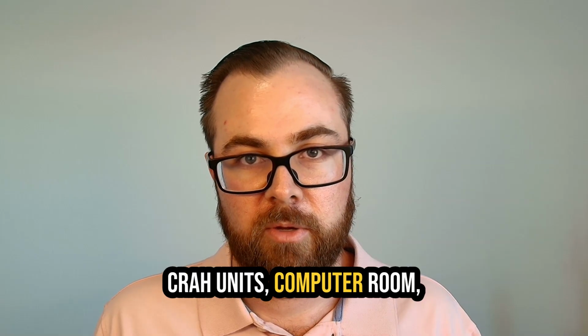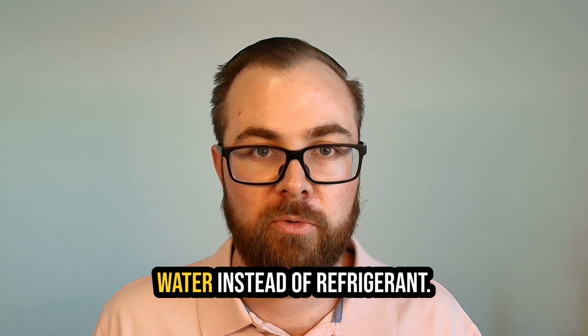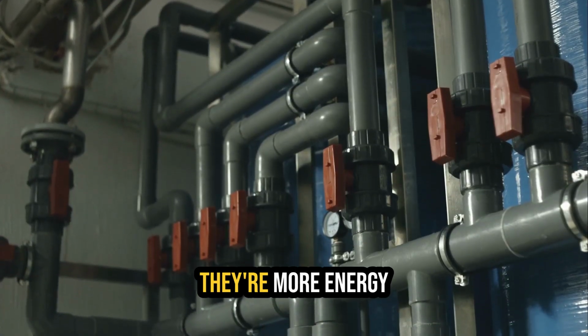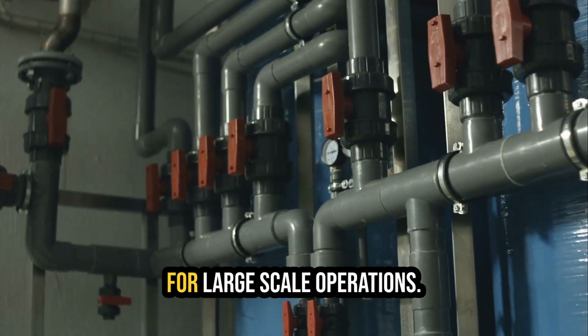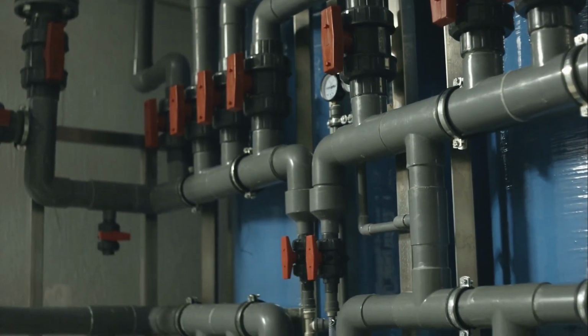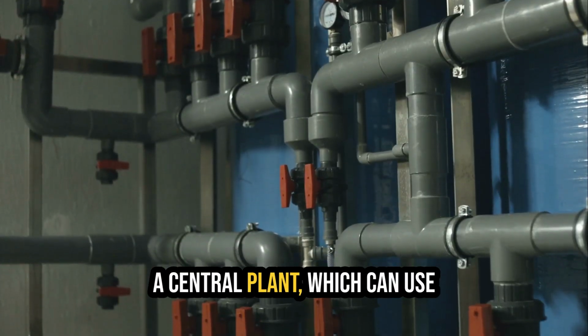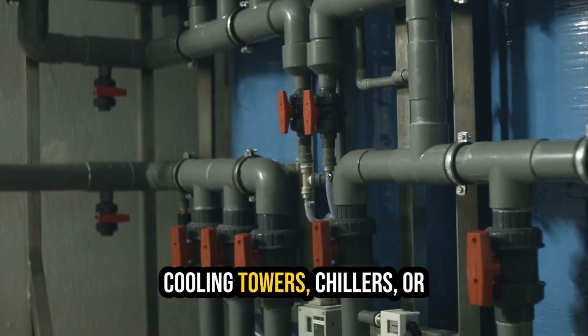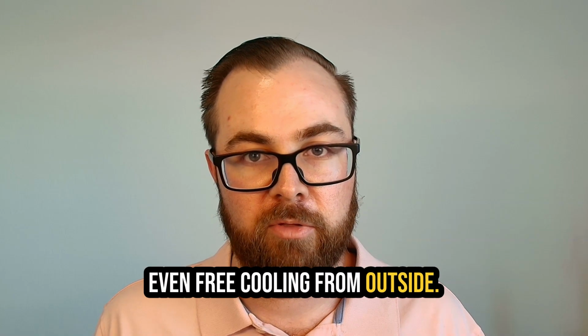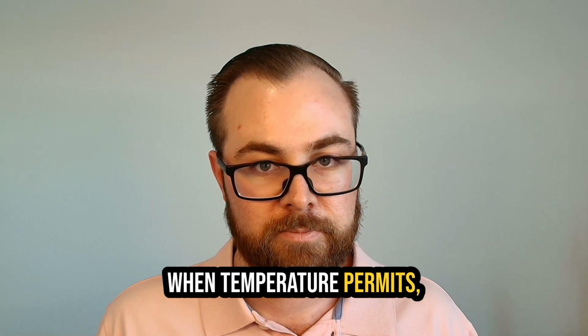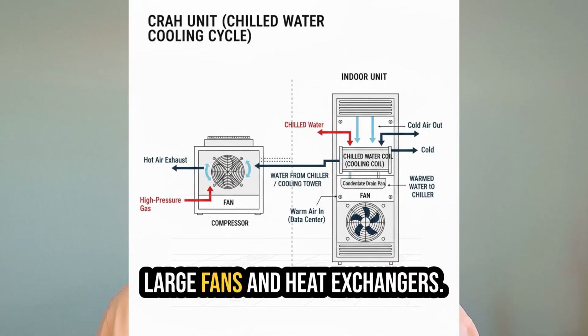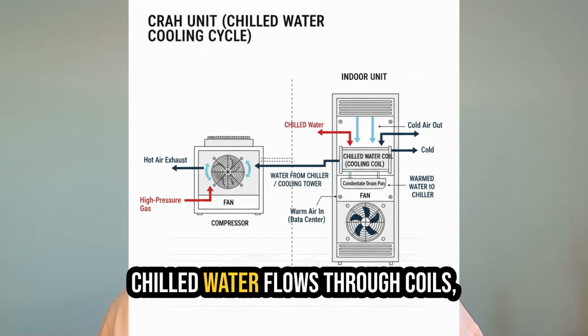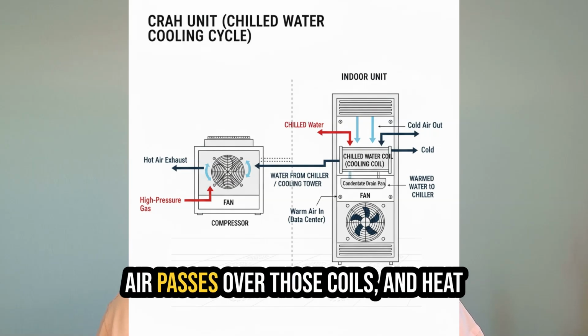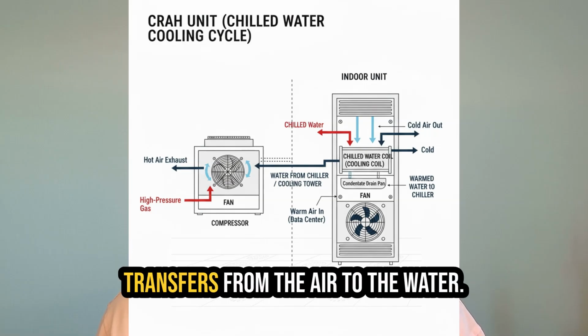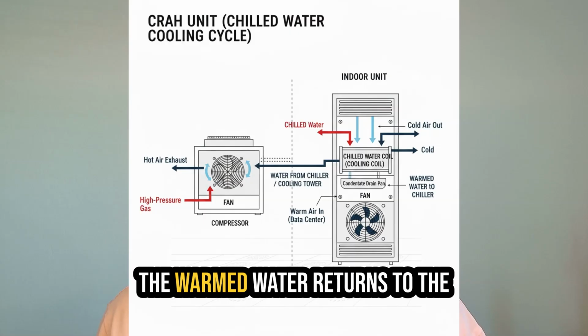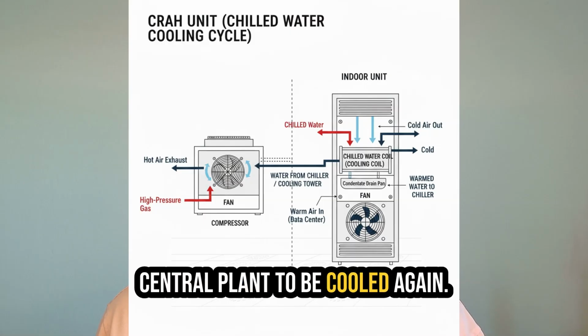CRAH units, computer room air handlers, use chilled water instead of refrigerant. They're more energy efficient and better suited for large-scale operations. The chilled water comes from a central plant, which can use cooling towers, chillers, or even free cooling from outside when temperature permits. CRAH units are essentially large fans and heat exchangers. Chilled water flows through coils, air passes over those coils, and heat transfers from the air to the water. The warmed water returns to the central plant to be cooled again.